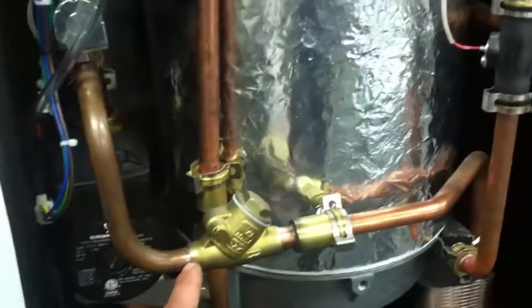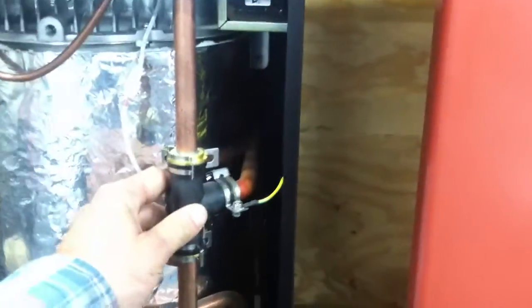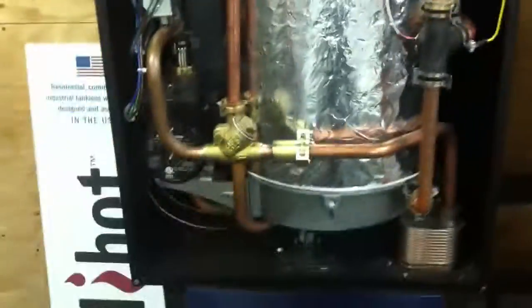It's got a small Y strainer, a good Grundfos pump, and a flat plate heat exchanger since this is the combi unit. That flat plate heat exchanger is on the bottom and easy to get to. You've got a 3-way mixing valve here, and all the electronics are up at the top, which we like - the fan and gas valve are in the top portion, so if anything leaks, the water goes to the bottom.